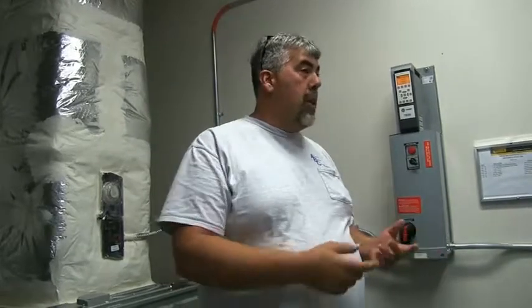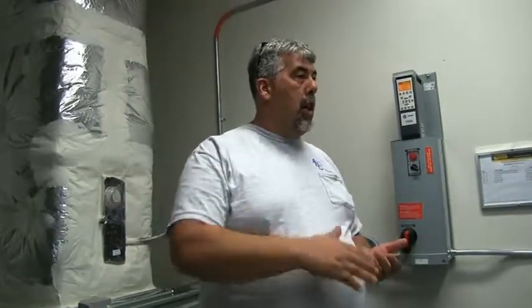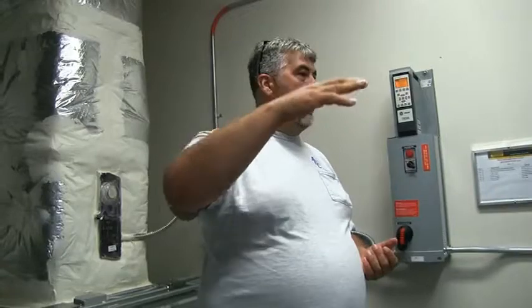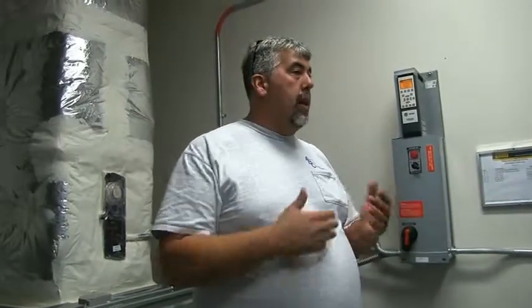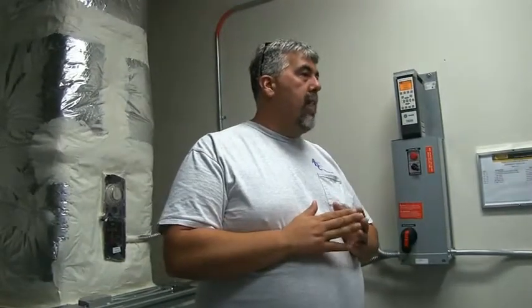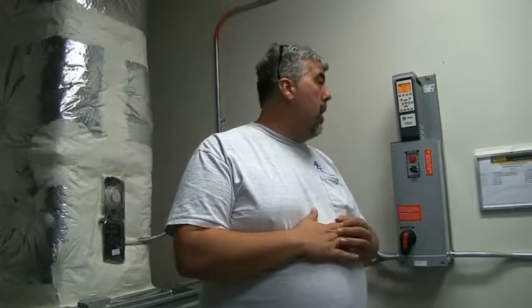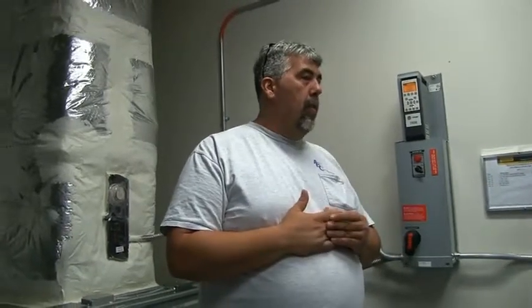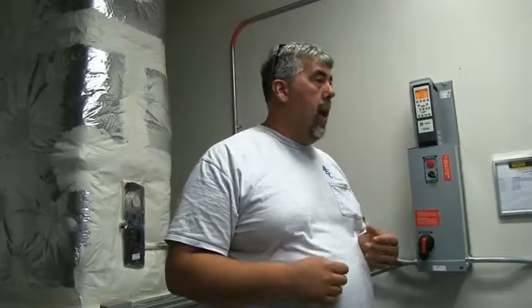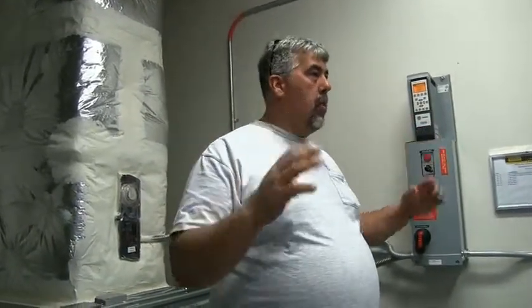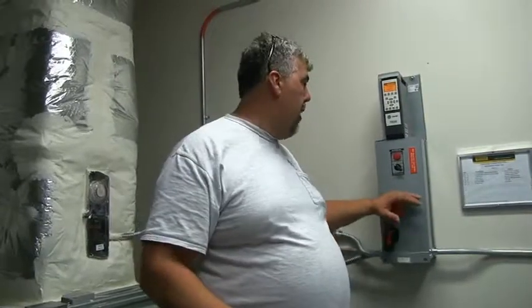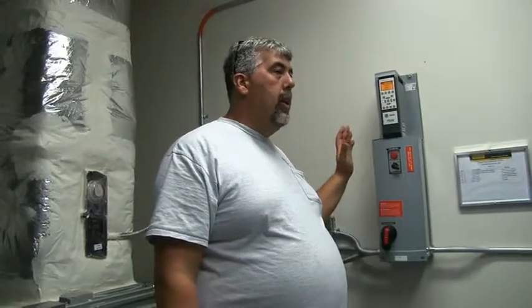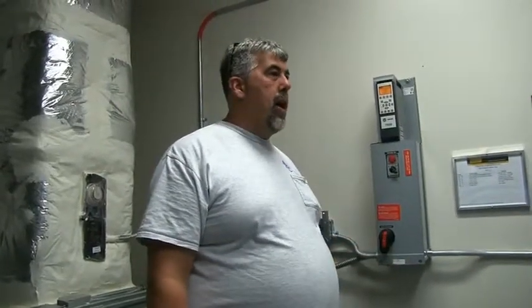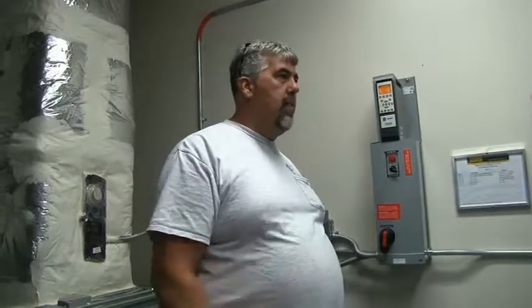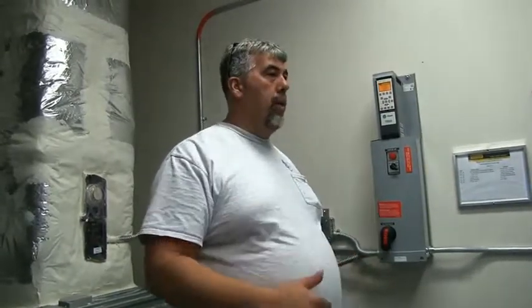Once a box goes above 76%, I'm going to start incrementing it up 1/10 at a time. Every day it resets back to the nominal, and that'll be a final number that I will get from TAB. You know what I mean? What they do, their total flow and worst case box, that'll be my starting point every day. I'll go to here, start my sequences. The fan will operate to that speed until 15 minutes goes by and it says, okay, all my boxes are below 65%. I can start incrementing down again.